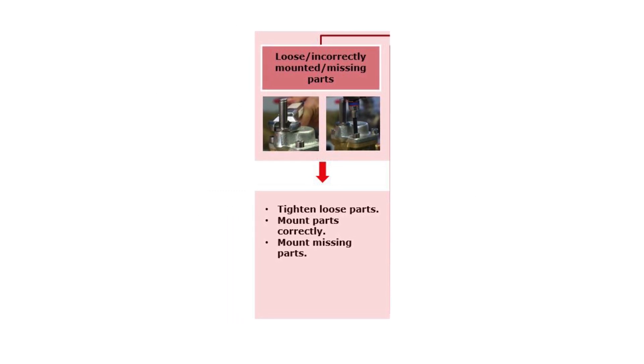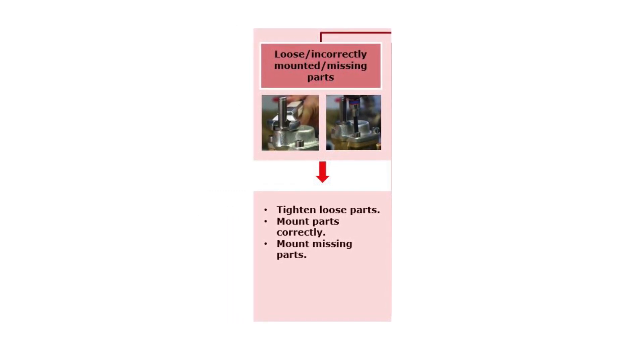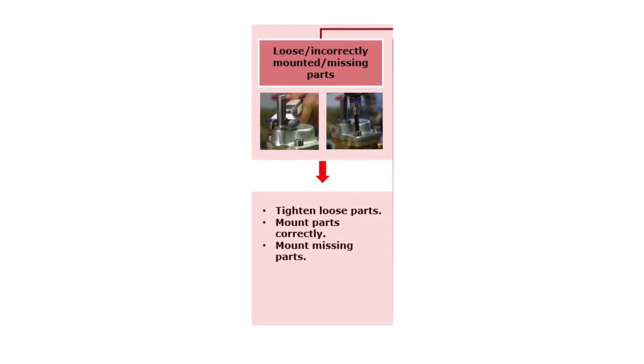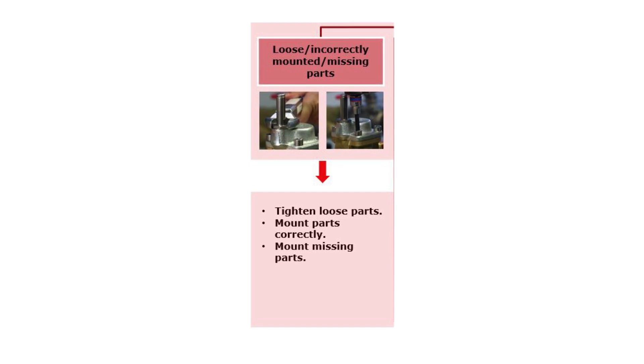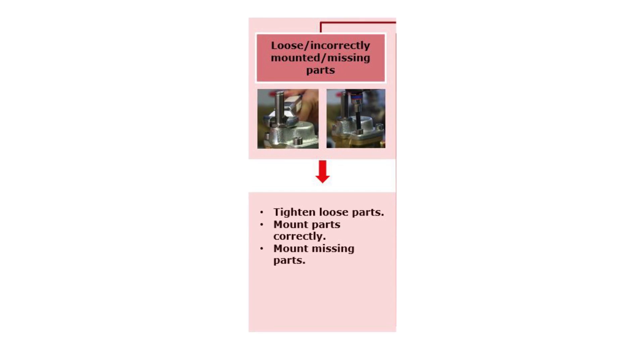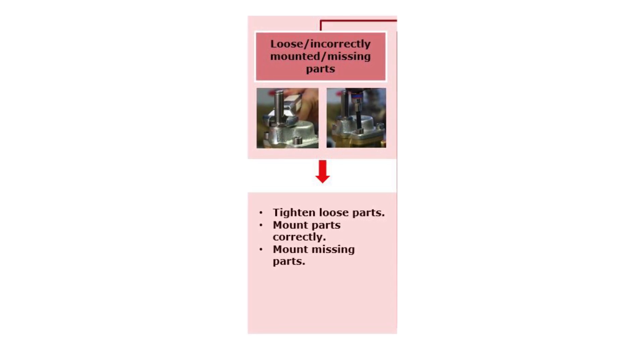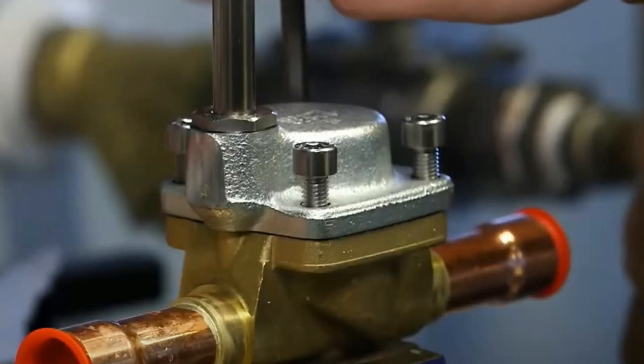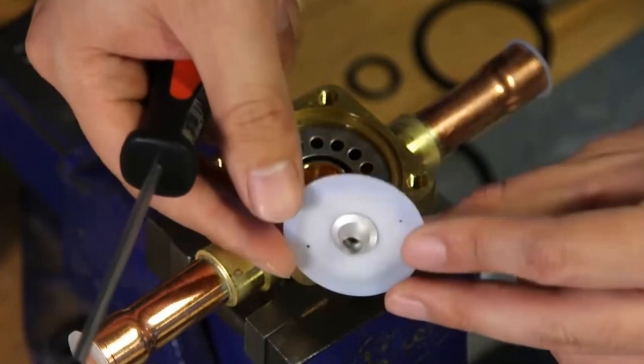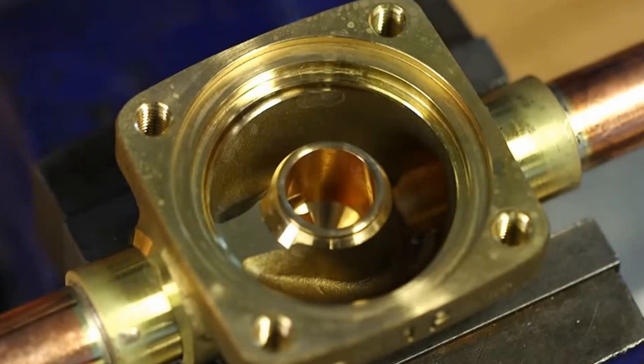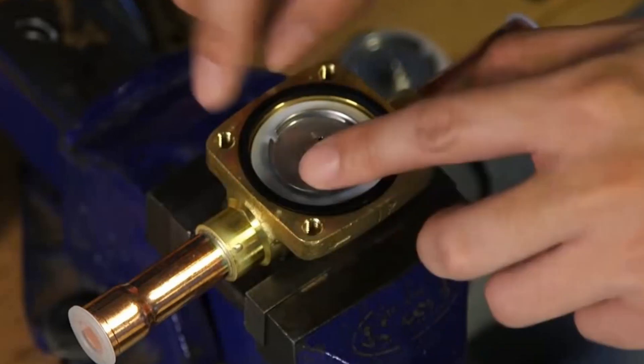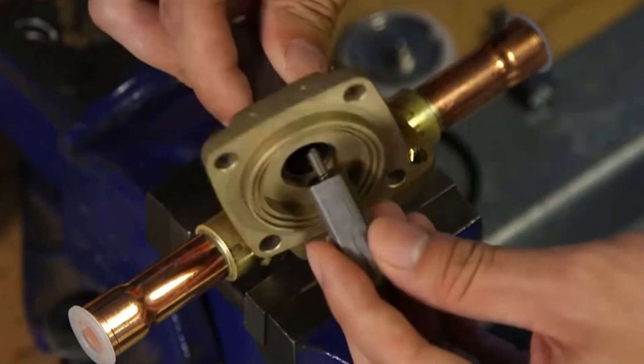Now, if there seems to be loose or incorrectly mounted parts, or maybe missing parts, after earlier service or inspection causing valve external leakage, then as a first step, tighten possible parts as seen shortly here. And if needed, take the valve apart, if it is serviceable, and ensure that valve parts are mounted correctly and possible missing parts are mounted, as seen shortly here.